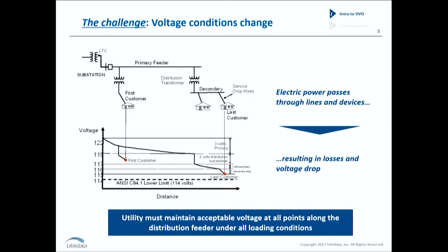So why do we have to do anything about voltage? There are a few underlying realities. The utility has to deliver acceptable voltage within standards at all points along the grid, at all times of year, under all loading conditions. Voltage conditions aren't consistent across the line—we see losses through devices as power is dropped to homes and businesses—and there's uncertainty about loading conditions, about when people turn things on and off throughout the day.